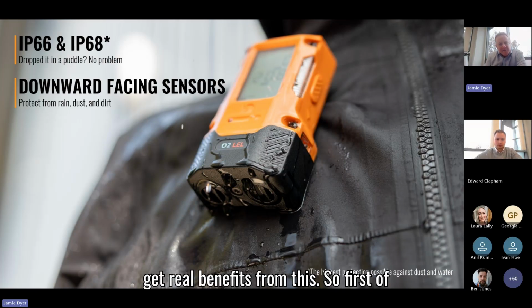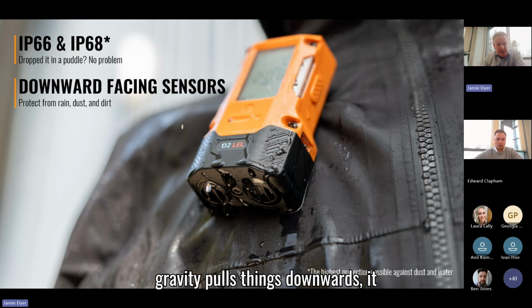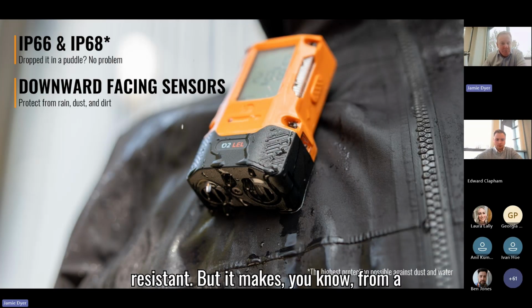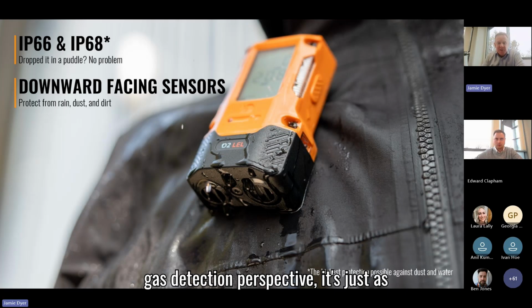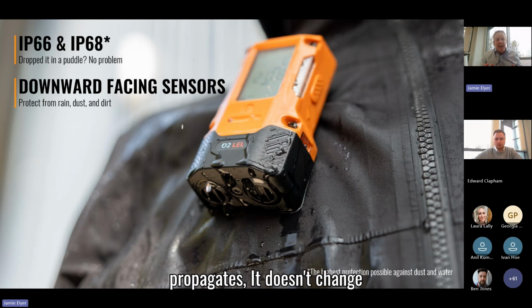But you get real benefits from this. First of all, it makes it much more resistant to water and dust ingress. If you think gravity pulls things downwards, those sensors are more resistant. But it's just as good from a gas detection perspective - if you think about the fixed gas detection world, you already have downward facing sensors, so as gas propagates, it doesn't change how quickly the device can detect gas.